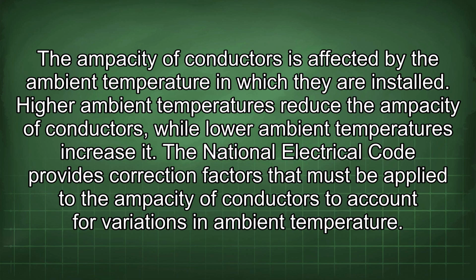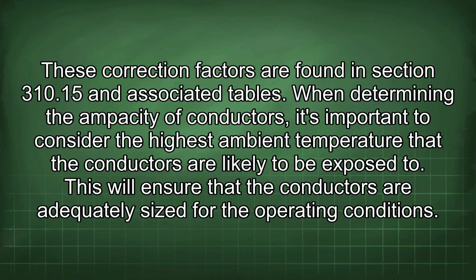The National Electrical Code provides correction factors that must be applied to the ampacity of conductors to account for variations in ambient temperature. These correction factors are found in Section 310.15 and associated tables. When determining the ampacity of conductors, it's important to consider the highest ambient temperature that the conductors are likely to be exposed to. This will ensure that the conductors are adequately sized for the operating conditions.